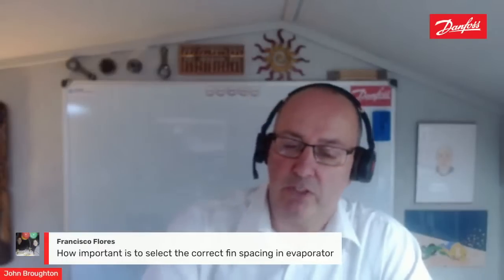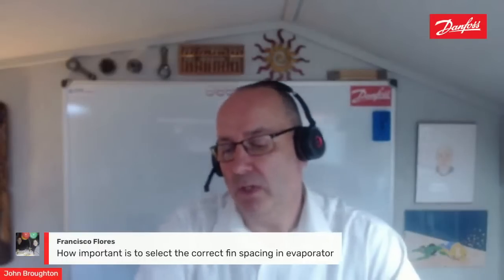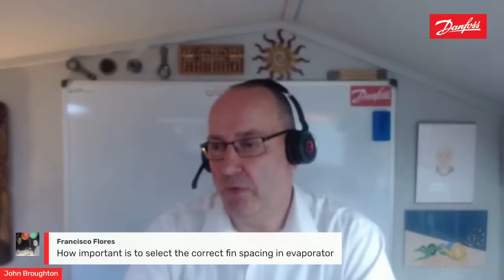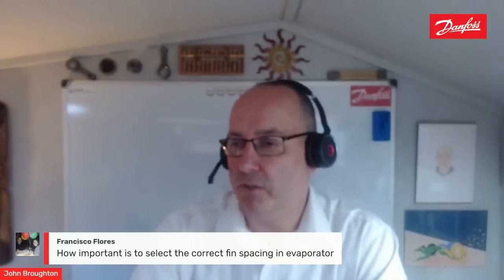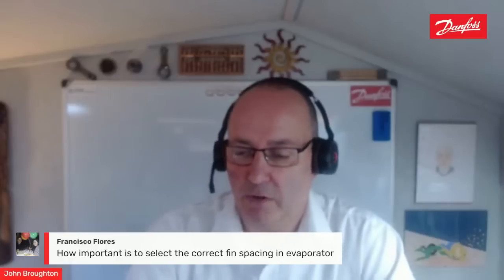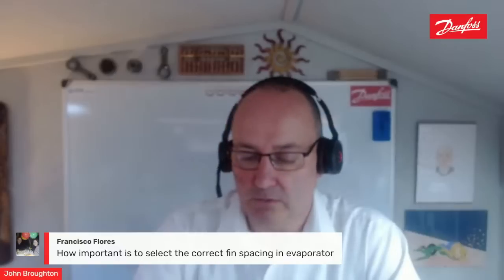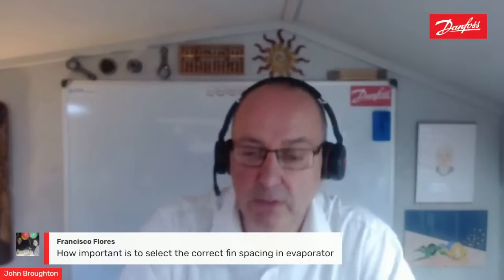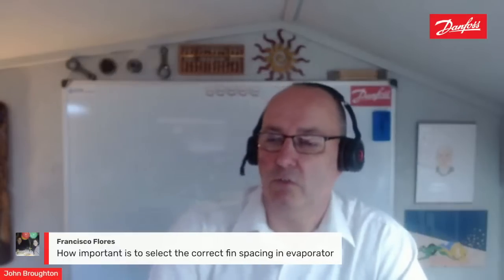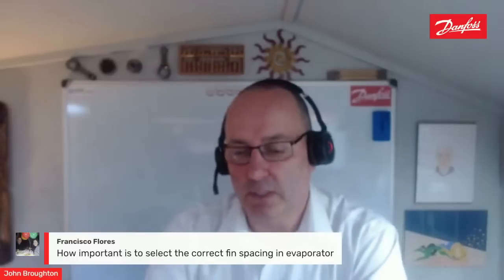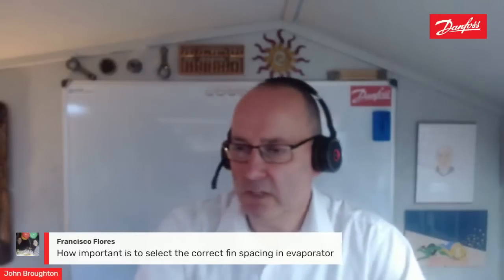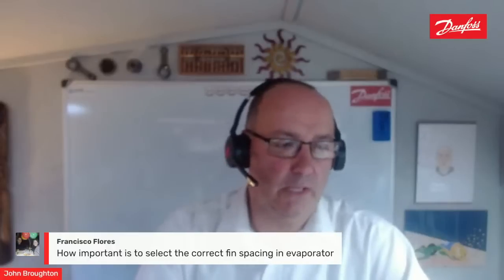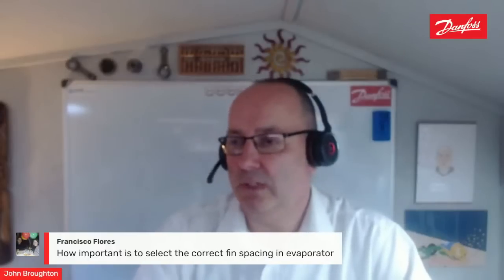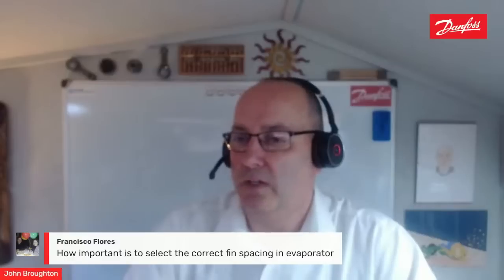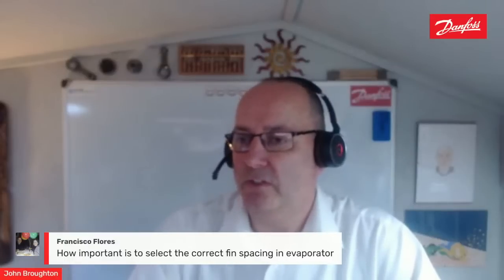So it depends on the evaporating temperature. The lower the evaporating temperature, the fewer fins per inch, and the higher the evaporating temperature, the more fins per inch that we have. So yeah, again, very important. If you speak to your local evaporator manufacturer, they will give you guidance on what is the correct fin spacing to have. I've got some data somewhere in another presentation, but that's a quick and direct answer, I think, Francisco.